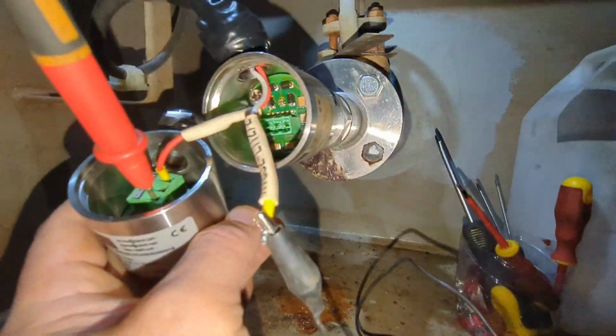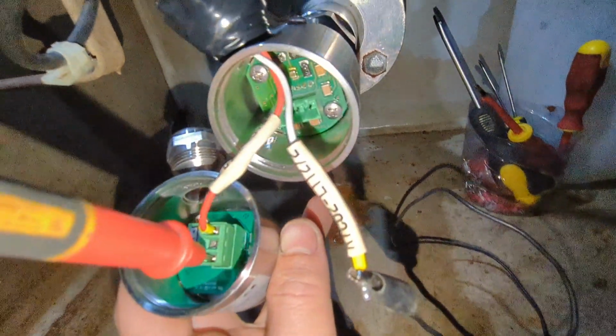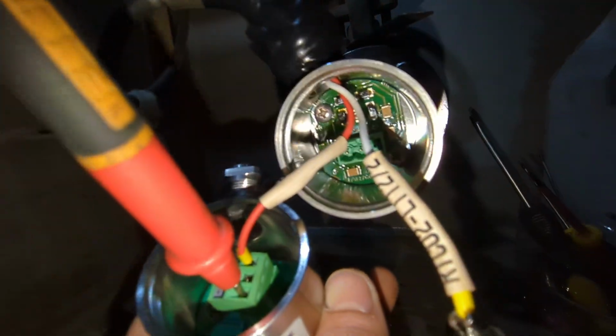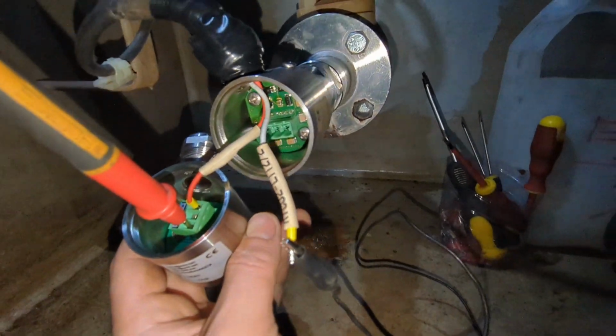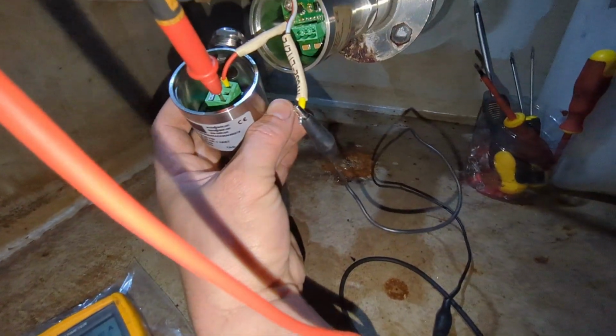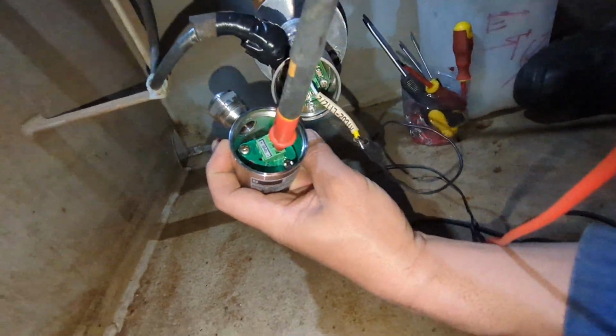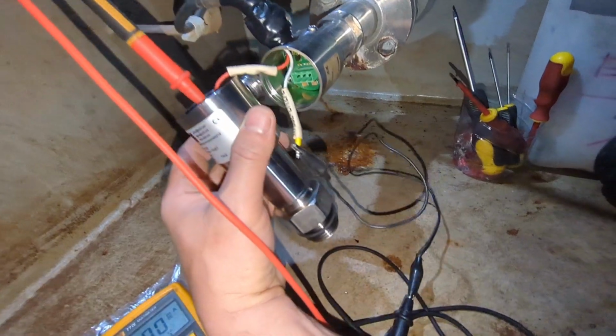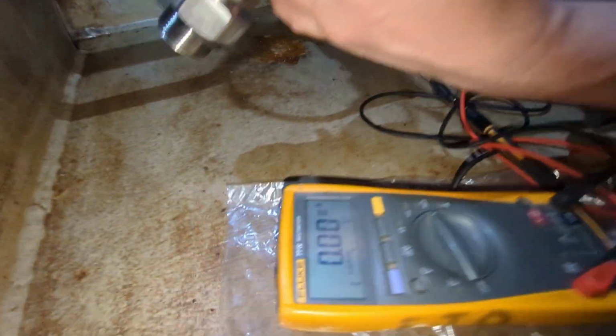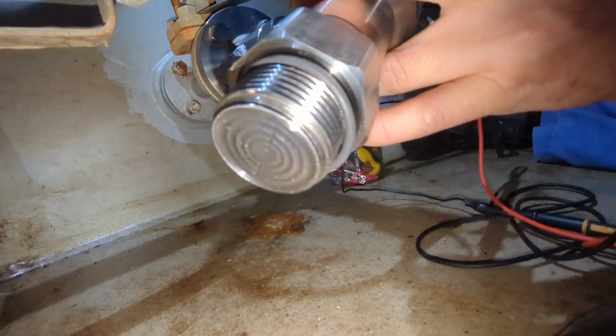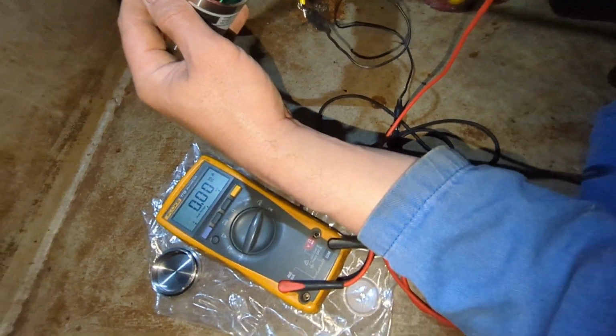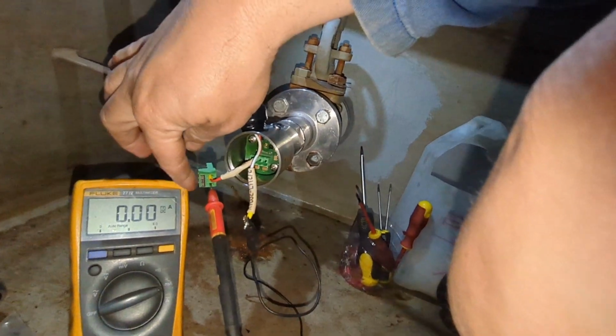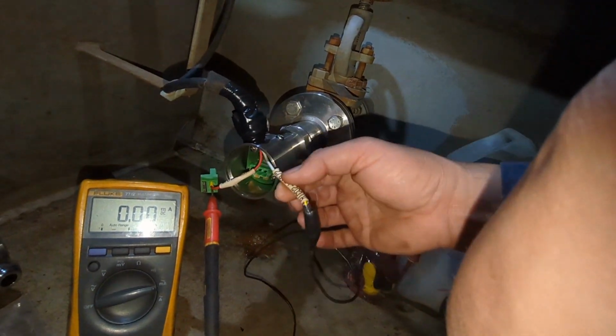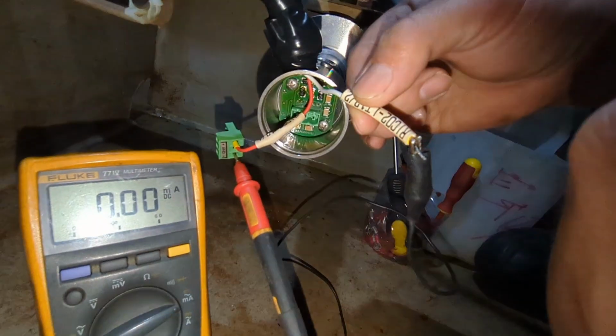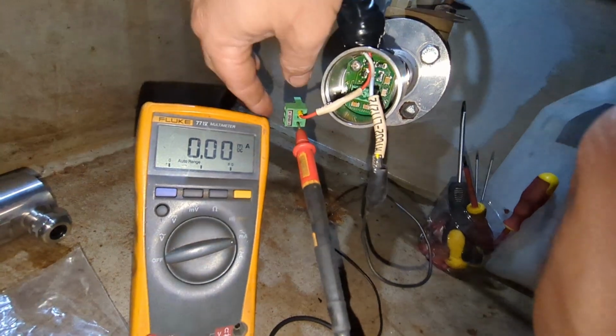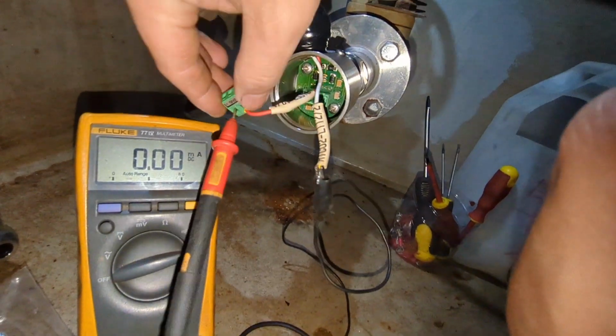As I compared it, I have here the old one, and I have here a new one. So I'm going to look why this has no milliampere value, because this has no pressure on the sensing side. I'm going to put back the terminals on the old sensor, and we look further how much the milliampere value is. So we can put this one and insert on the terminal.